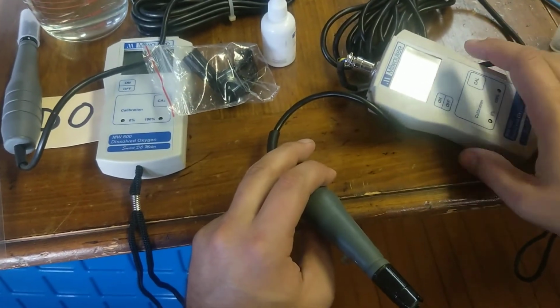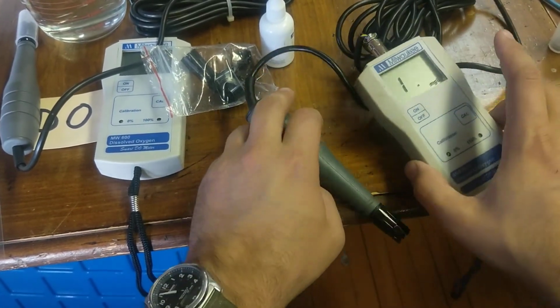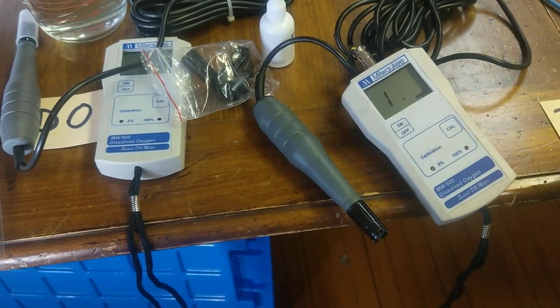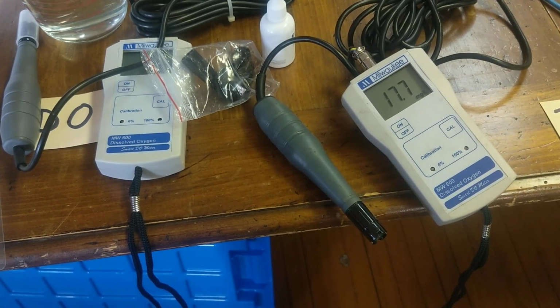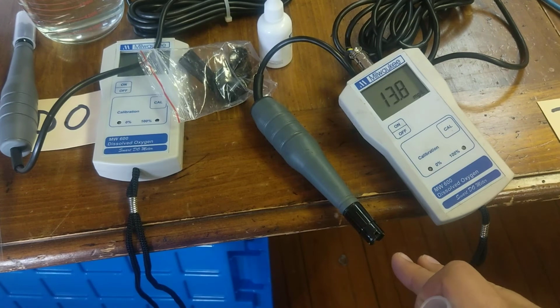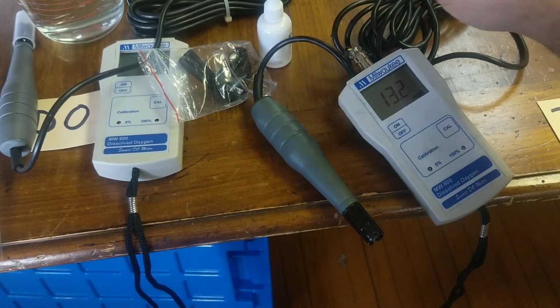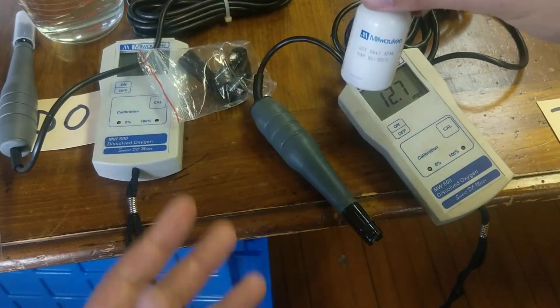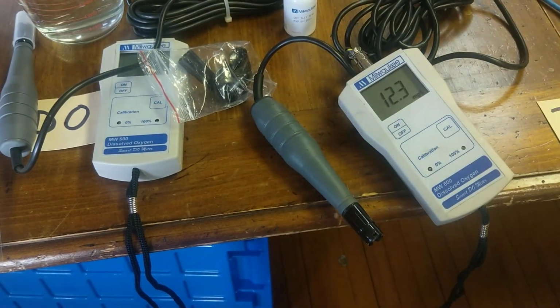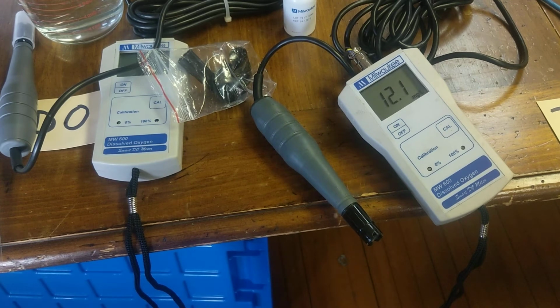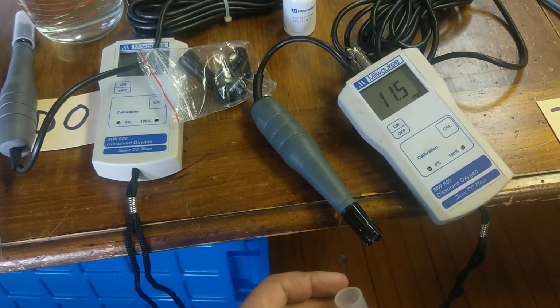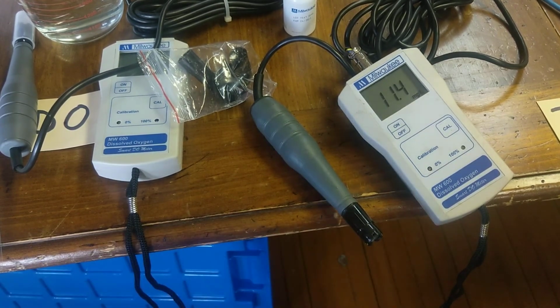Before you calibrate it, though, you need to turn it on and let it go for a little bit. And you need to do this for 15 minutes. Just so that, if there's any oxygen in this fluid, it will burn up that oxygen. So you kind of have to let it go for a little bit. 5 to 15 minutes. Once that's done, you can do one of 2 things.